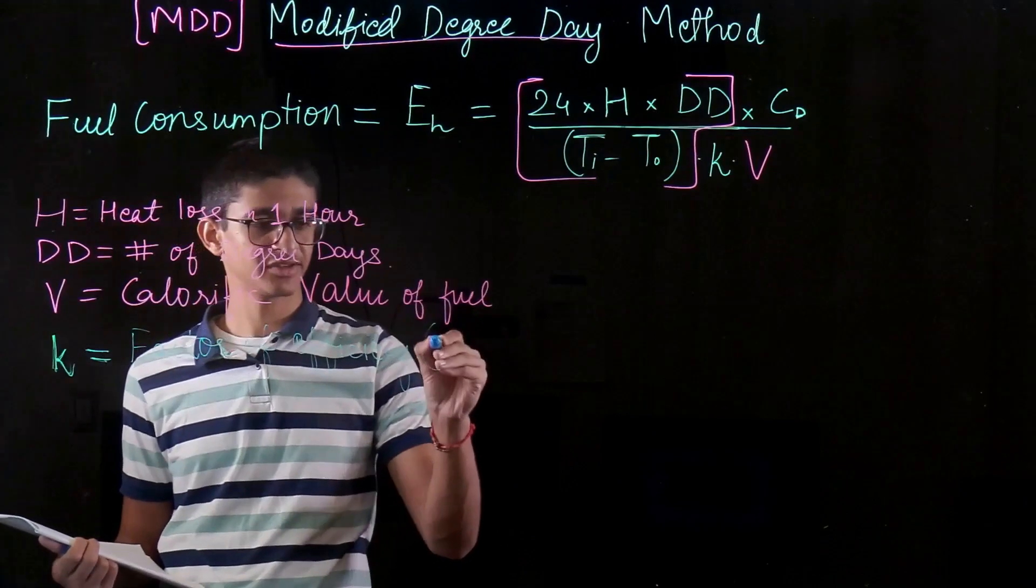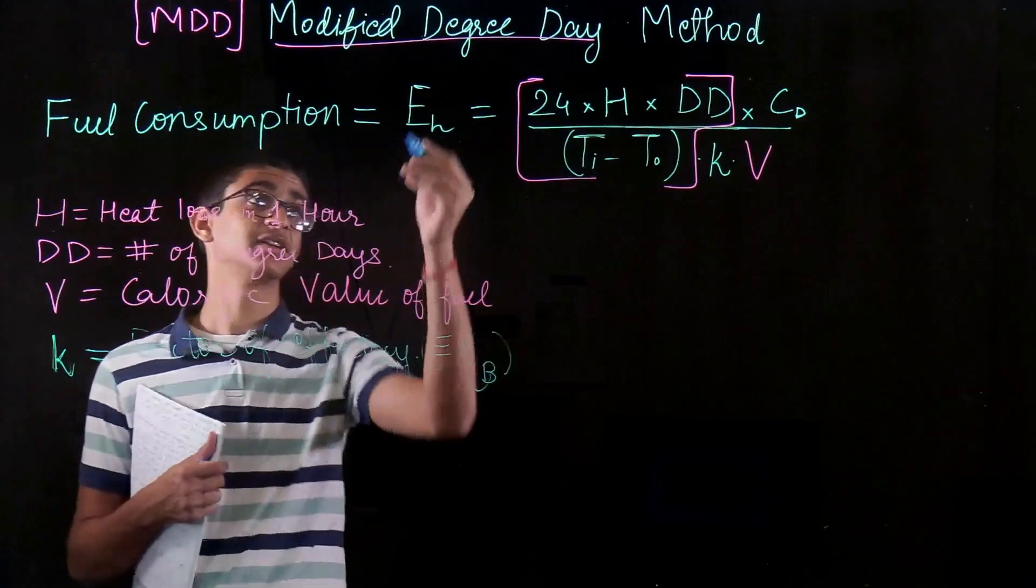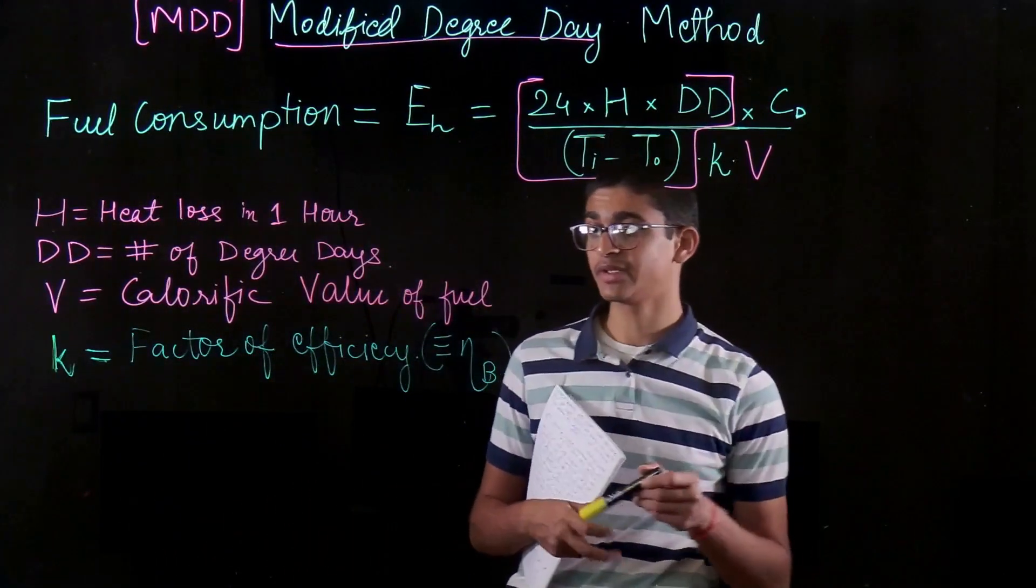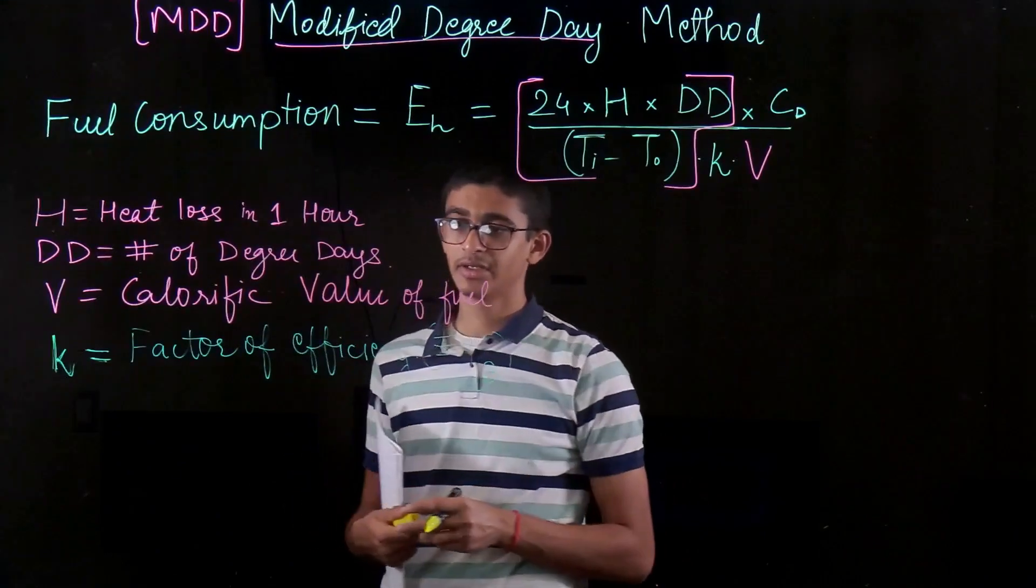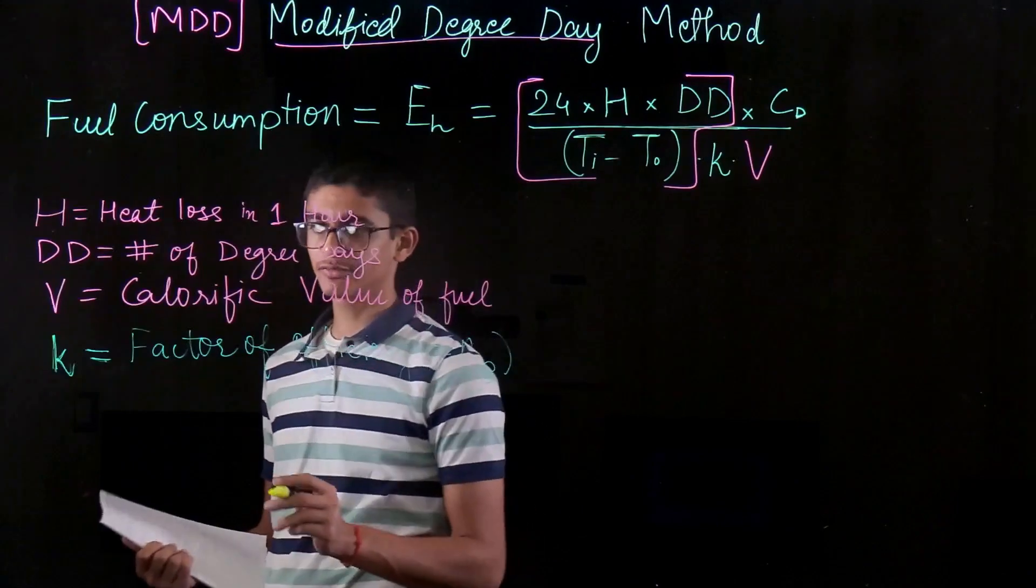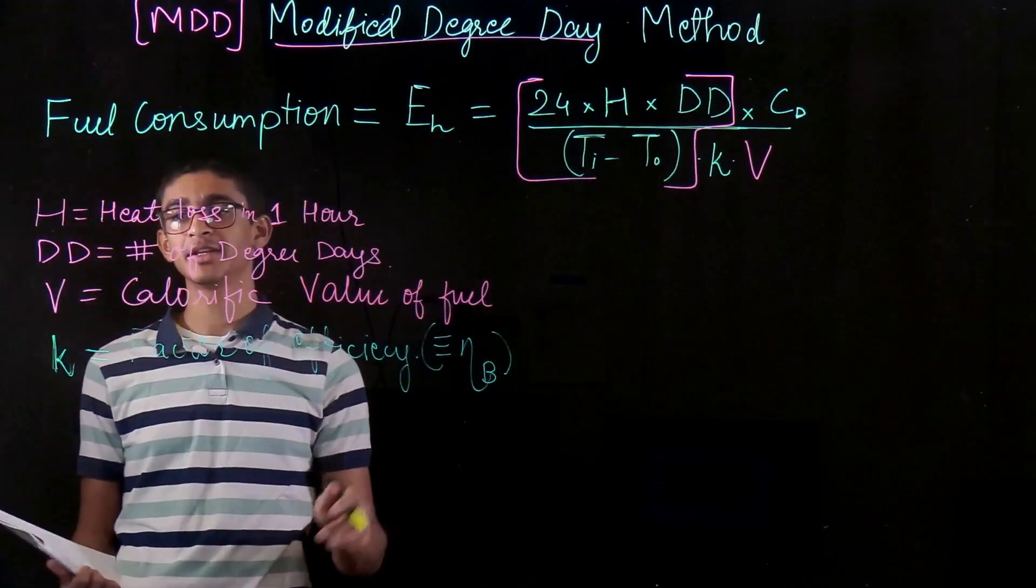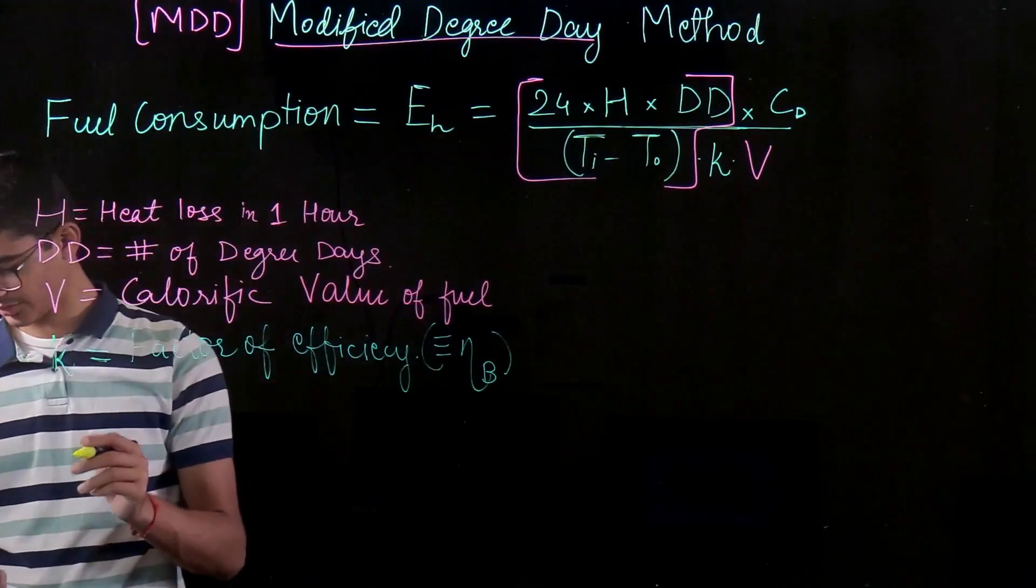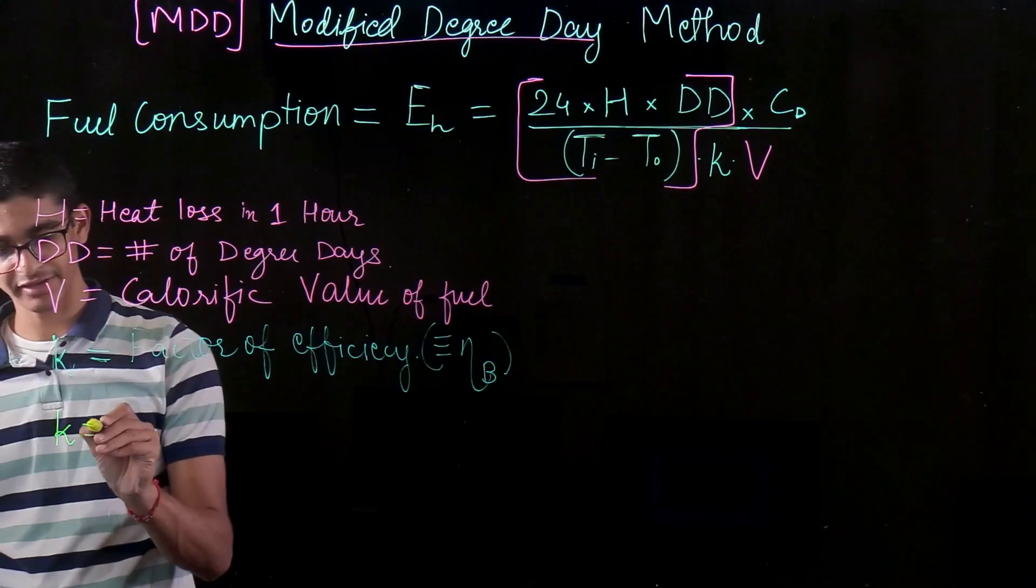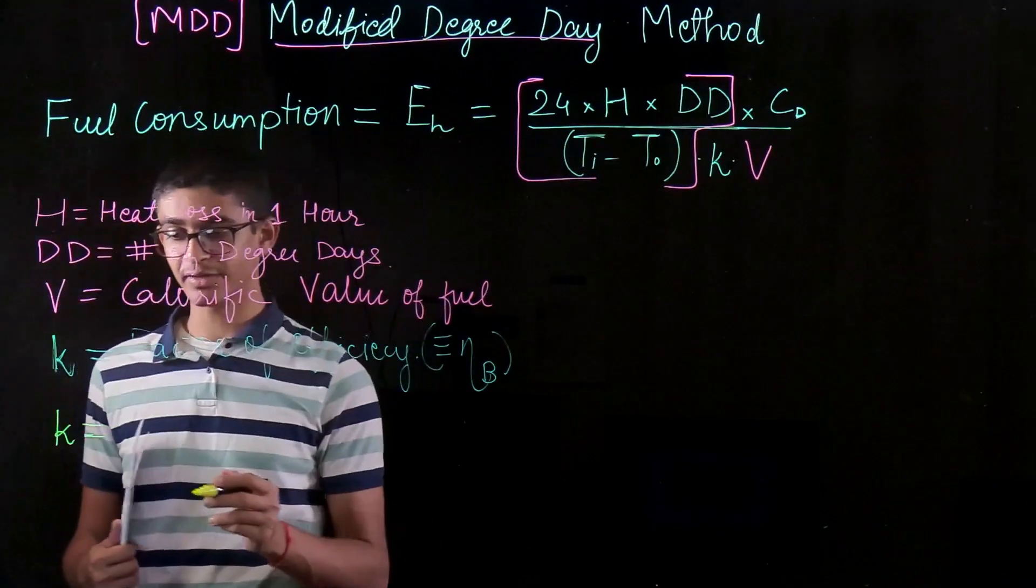Which is very much similar to what we had efficiency of the boiler in the previous case of degree day method. But as I said, it is one of the disadvantages of that method that we are assuming a constant efficiency of our boiler, which might not be the case for all the boilers. Because if we are operating the boiler at part loads, the efficiency keeps on changing. The efficiency might reduce. So my K factor now takes into account those changes in the efficiency based on part load and based on the technology which we are using.